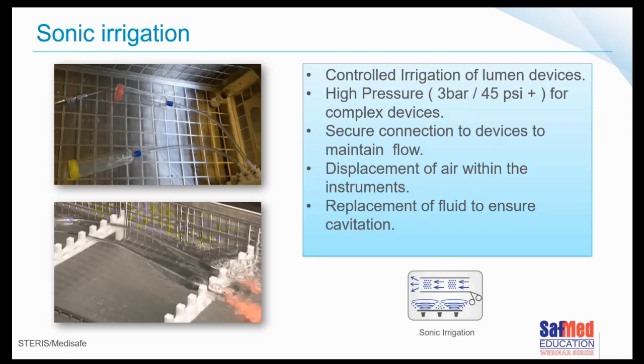So what you're going to be doing is taking your instruments, let's get out the pointer again, you're going to attach them to this device over here, either using this kind of distal connector or perhaps a luer lock, depending on what's going to fit. And then at the end of the day, you'll have sonics on the outside of the instrument as well as flushed down the actual lumens. As you can see over here, all the debris coming out over here. Pity you can't see the pointer, sorry about that. But what I'm alluding to, I'll try to describe it. If you look at the images on the top, on the left, there's a device there called a distal connector. It comes in different diameters so that you can put the nose of your suction irrigation in there so that the sonics end up flushing down the lumen of all of your instruments.